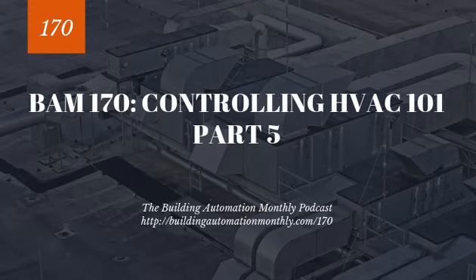And you're going to see that this is going to look like low DeltaT, but you're at full load and you're at design. And so how is it low DeltaT? How is it a low DeltaT syndrome? It's actually not. This is usually a sign of poor maintenance on the actual pumping and piping system itself. So you want to be cognizant of that as you go and troubleshoot systems, especially this summer when some of you, depending on where you're at, are going to be running into systems that are fully loaded. If it is an older building, this is something I would definitely be cognizant of.